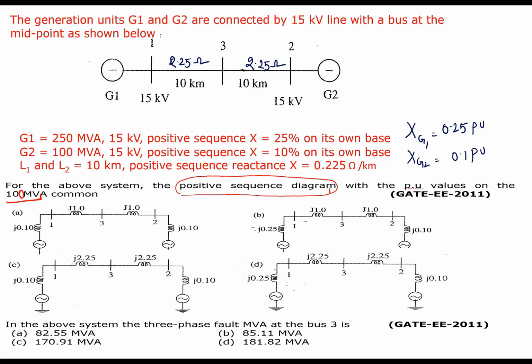Why? Because the entire network is at the same voltage. Here voltage is 15 kV, generator voltage is also 15 kV, transmission line voltage is also 15 kV, and generator G2 voltage is also 15 kV. So our base MVA is 100 MVA and the base voltage is 15 kV. Now we have to calculate the positive sequence network or per unit impedance diagram for the given power system network.